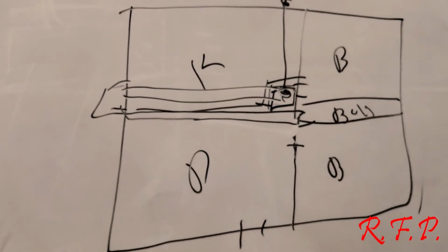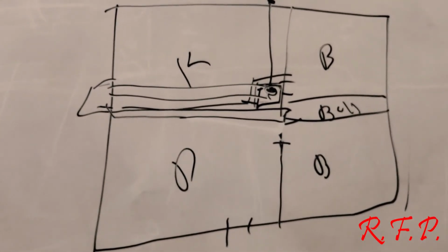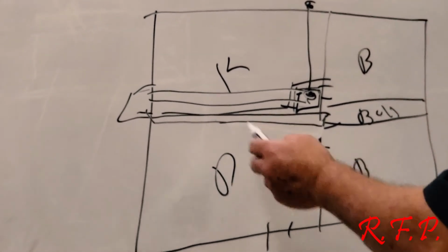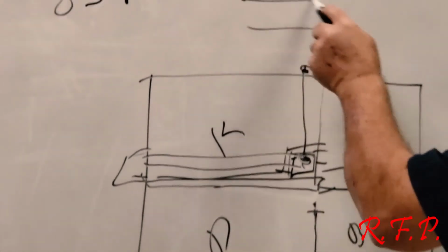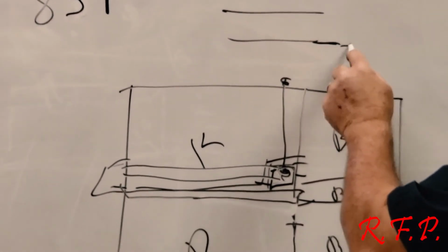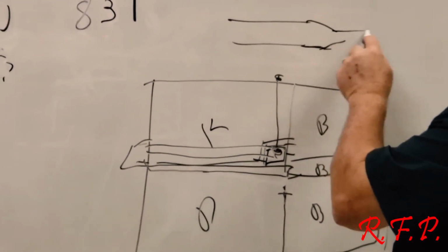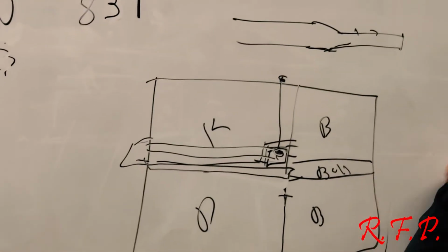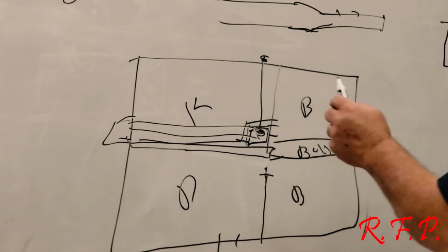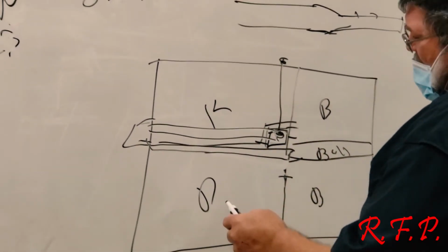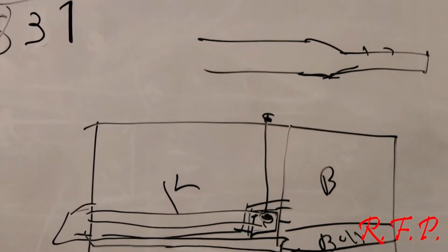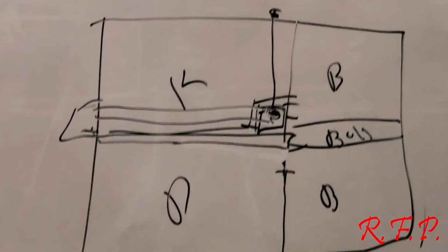But put a 2-ton unit on it. I may build a 12 and a 10. Put one section of 12 on it. I go up here and put one section of 12 on it or two. And then reduce down to 10. Build all this in the yard. Put the takeoffs on it. Then wrap it. Oh yeah, somebody did that. Put the takeoffs on it. Then wrap it. And get it all fixed up. And drag it under the floor.